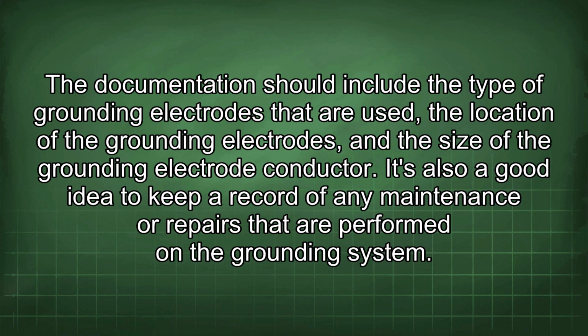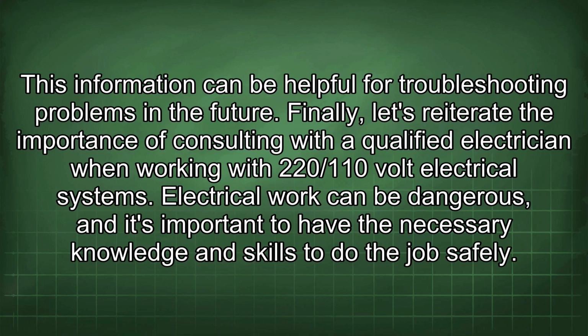The documentation should include the type of grounding electrodes that are used, the location of the grounding electrodes, and the size of the grounding electrode conductor. It's also a good idea to keep a record of any maintenance or repairs that are performed on the grounding system. This information can be helpful for troubleshooting problems in the future.